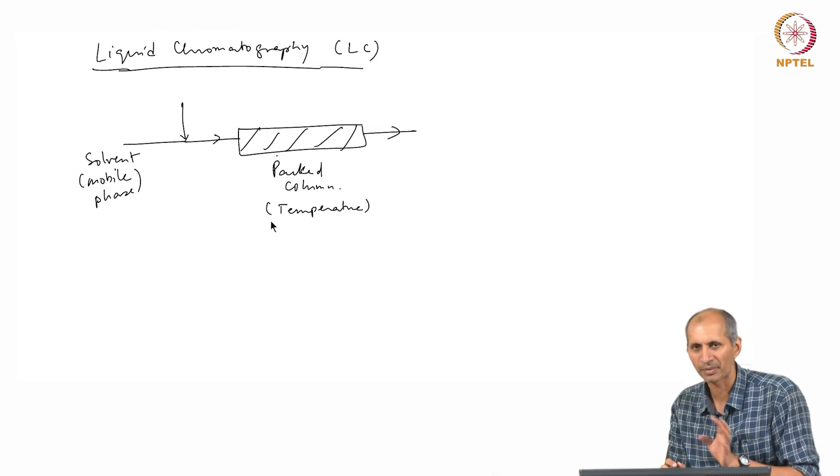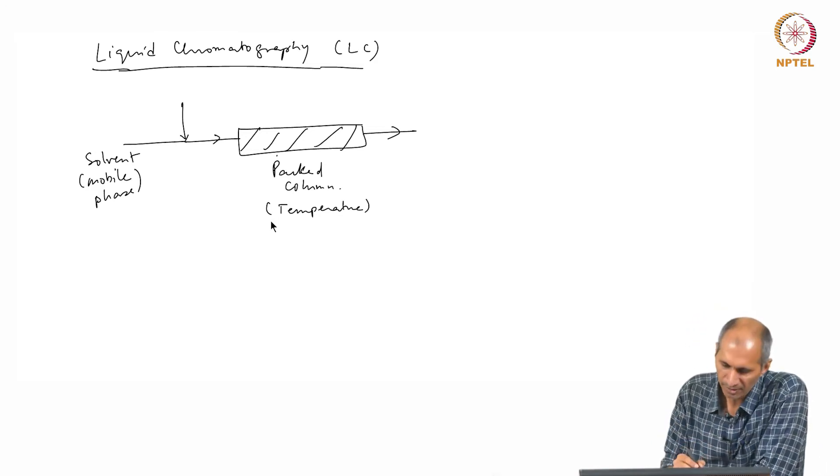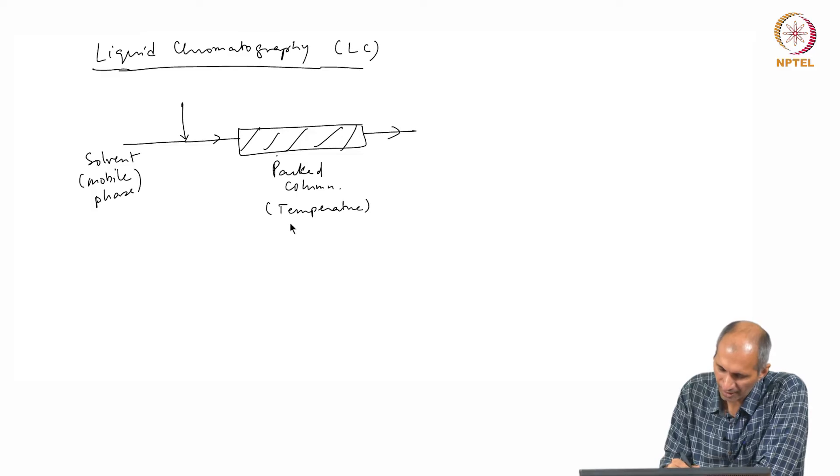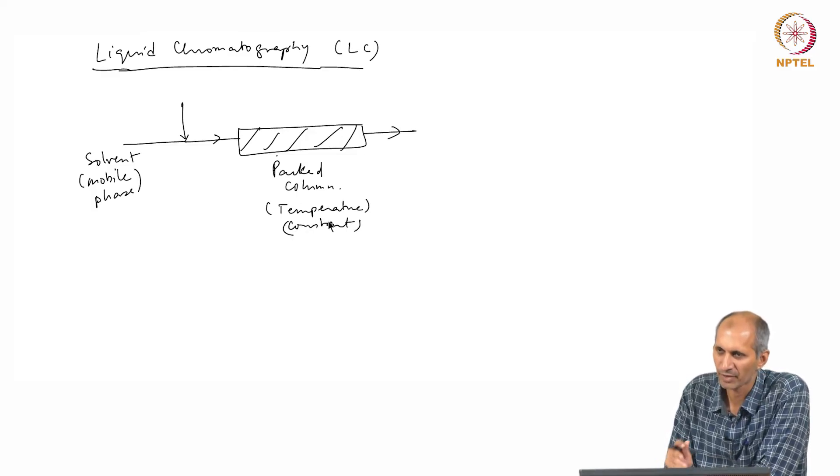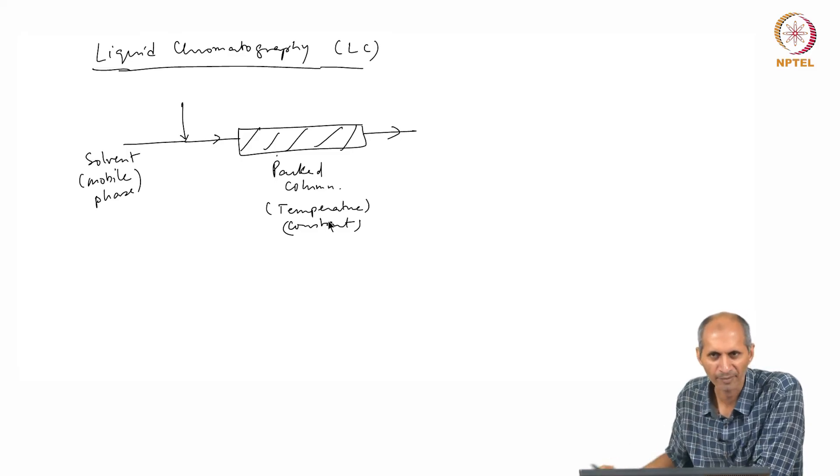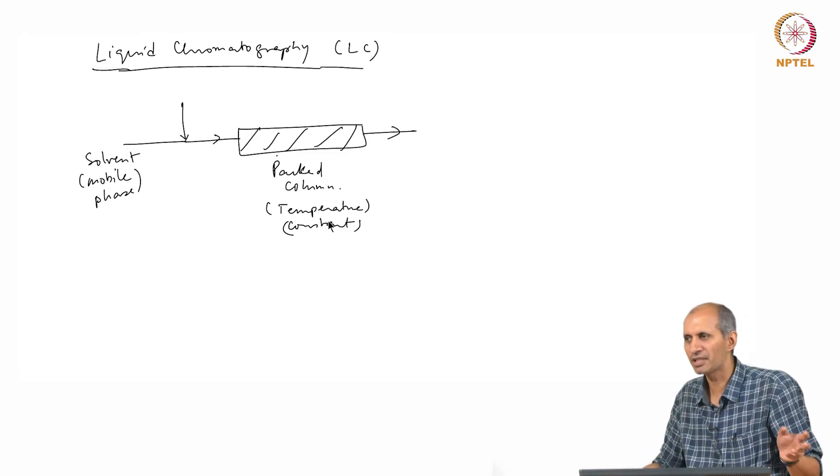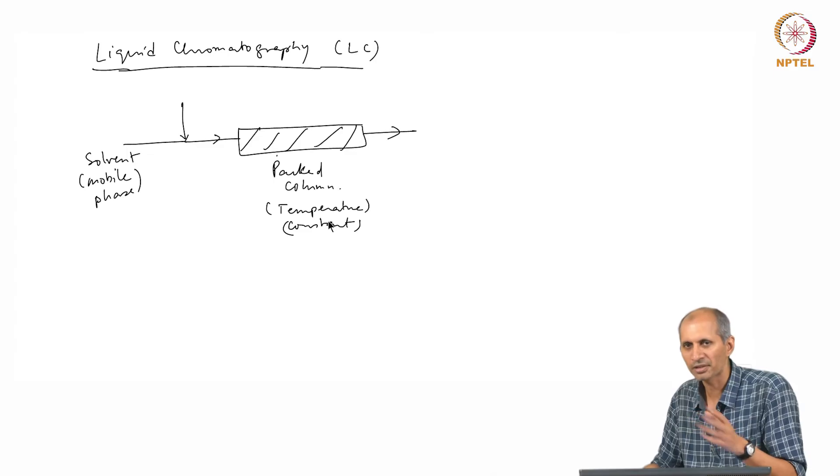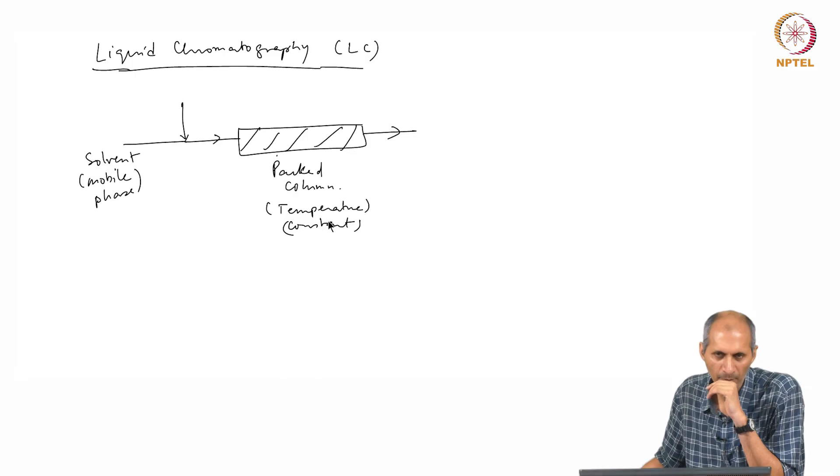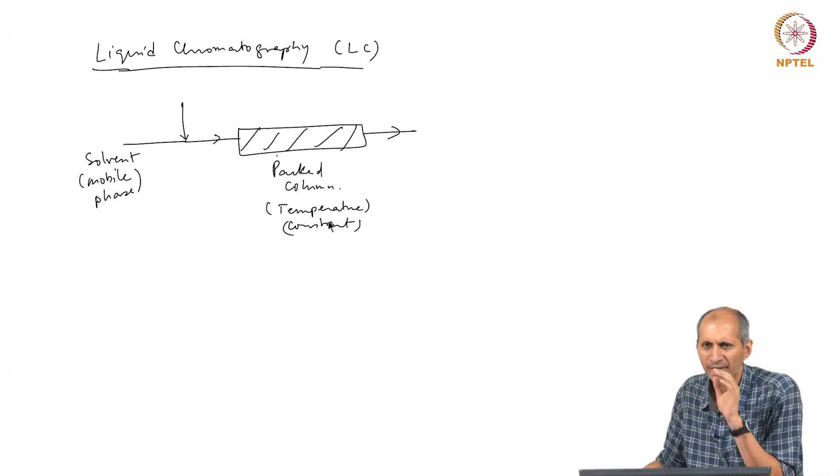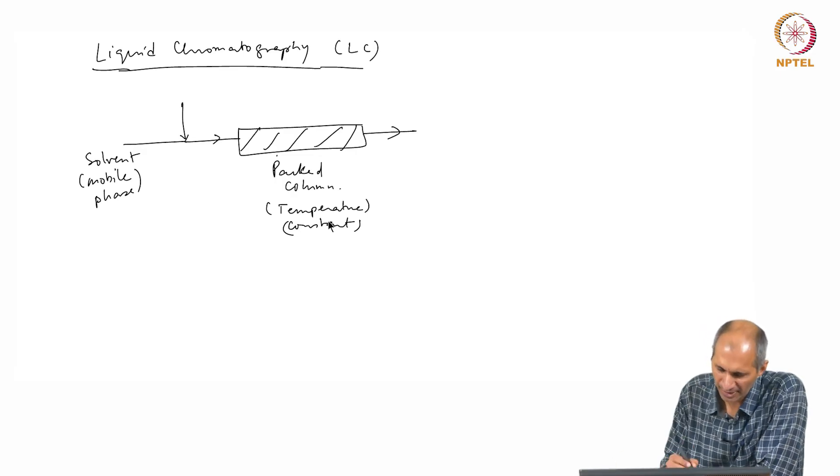You are basing everything on retention time and retention time changes because of flow non-uniformities which will occur because of bubbles. We do not want all that. Temperature people do not usually play around with liquid chromatography. Temperature is there usually to maintain constant temperature, that is all. The oven is there as a controller.